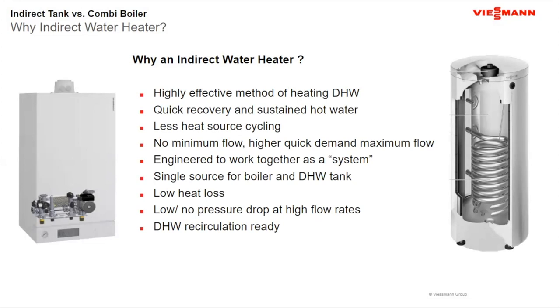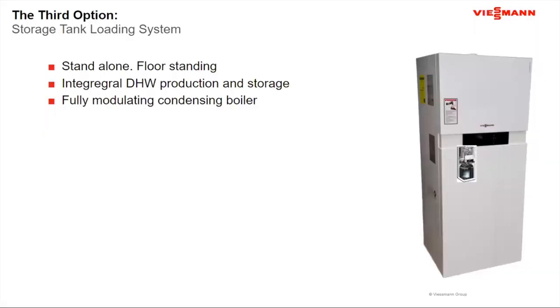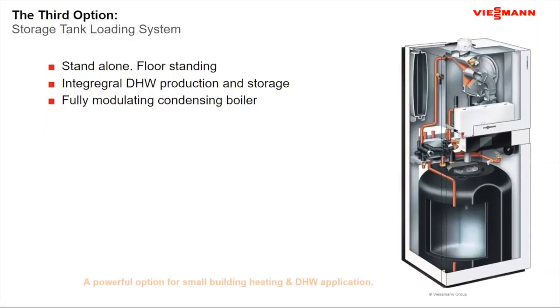Now, this is not to say that the combi boiler is fully discounted. The combi boiler has its place, and there are places that only a combi boiler can work. But when I get into houses like the one I used as our reference project, 4 bedrooms, 2.5 baths, I start to look at what that project represents, and the indirect water heater is usually the more intelligent choice for that style of load. I will say that with the exception of the third option, the storage tank loading system.